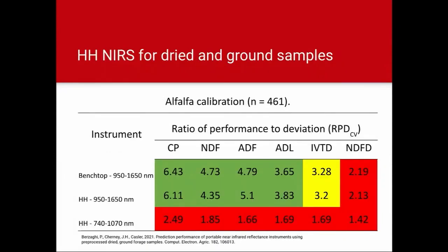Now, what happens if we compare benchtop instruments with handheld instruments? So this is the benchtop instrument with the wavelength range restricted to be the same as the first handheld instrument here, so from 950 to 1650 nanometers. And here we see that the RPD statistic would tell us that the instruments perform very similarly. We have even some cases where one does better than the other, so I would say that we're within kind of the noise of our experimental design here.